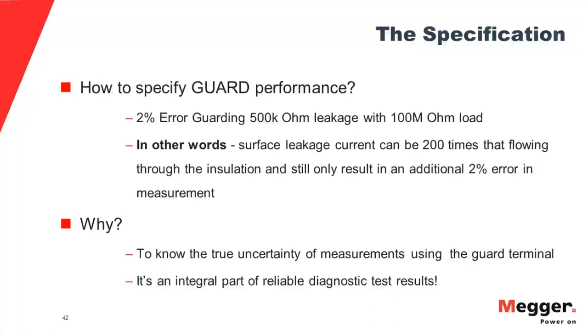What some manufacturers do is put a high resistance in the guard terminal circuit. This defeats the purpose of having the guard terminal. On the other hand, if you have it at low resistance, now you've got a potentially dangerous path into the instrument for your arc flash protection. So a low guard terminal resistance can defeat your arc flash protection, your IEC 1010 protection. So it's a balancing act between these two competing functions to design a good guard terminal.